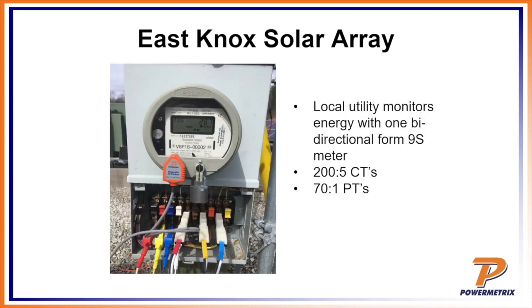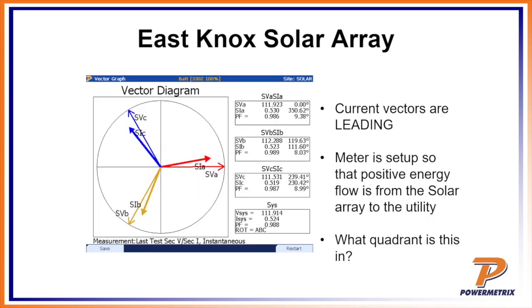So this one's kind of unusual, and I don't recommend this, and I apologize for calling the utility out. They did put a bidirectional meter in there, an Elster meter, which is a good meter, with 200:5 CTs and 70:1 PTs. However, when they wired up the secondary going to the meter, they flipped everything around. So when the meter is in generation mode, it's actually measuring as delivered. Their assumption is, well, it's always generating, so why flip it back around.